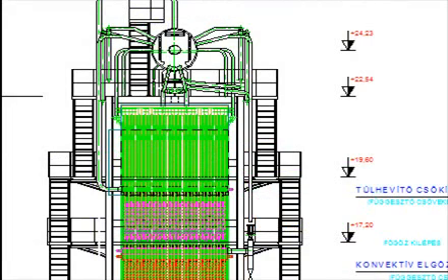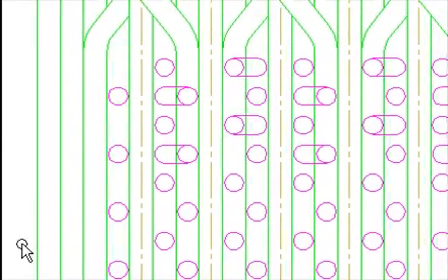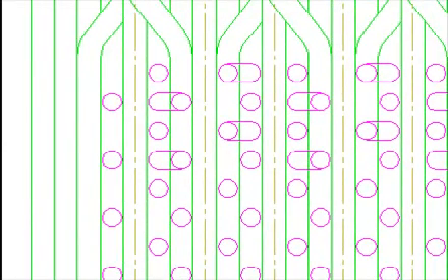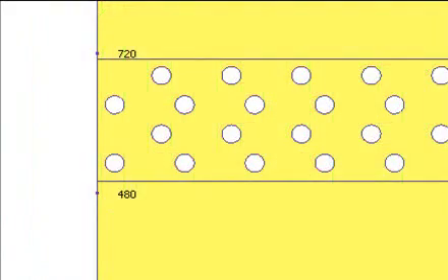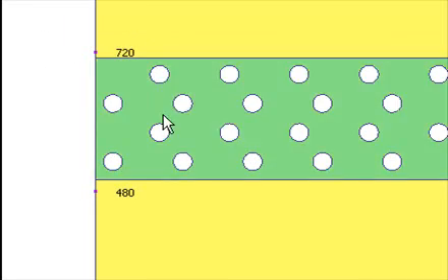But tube bundles mean certain resistance when flue gas flows in the block, so this resistance must be applied to the volume too. I made some two-dimensional simulations on partial geometry of tube bundles to calculate the pressure loss. In case of our steam generator, these 2D simulations were needed anyway, because the heat exchanger tubes were hanged on a steel structure, and this way every second row of tubes had to be shifted a bit. Because of that, we had a smaller and a bigger gap between tubes.